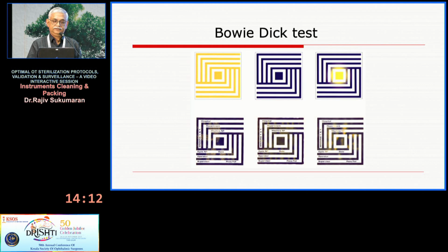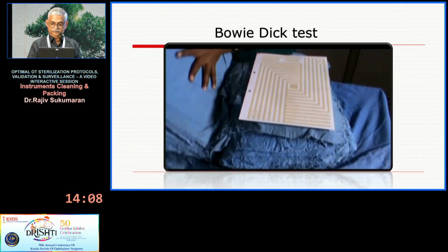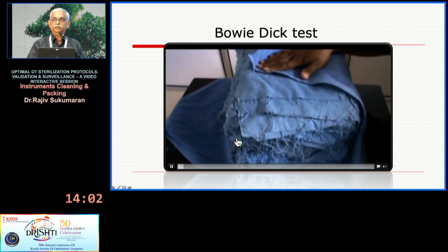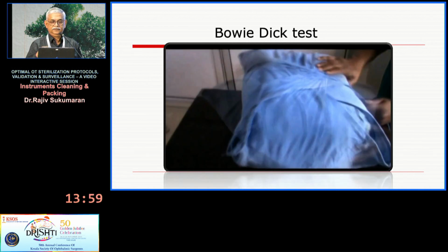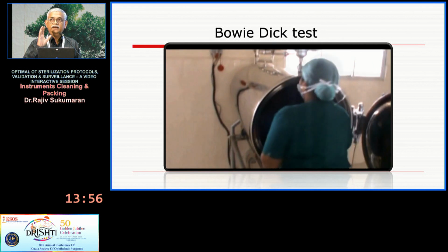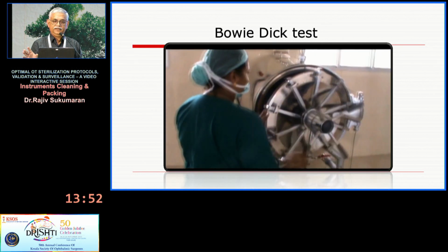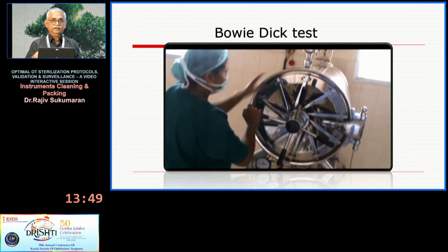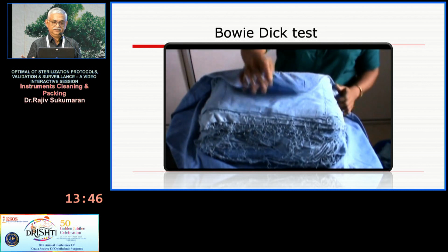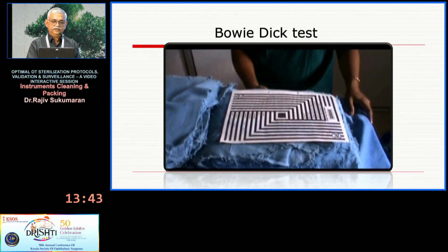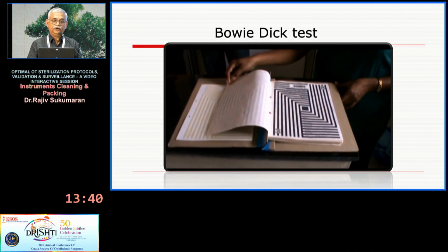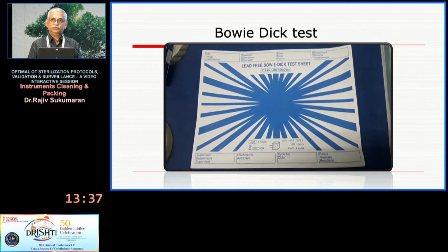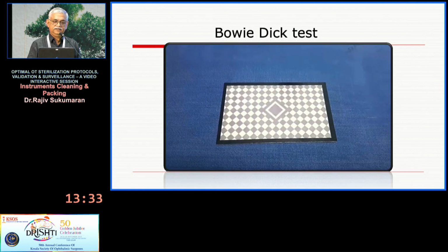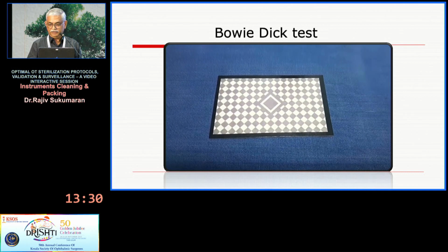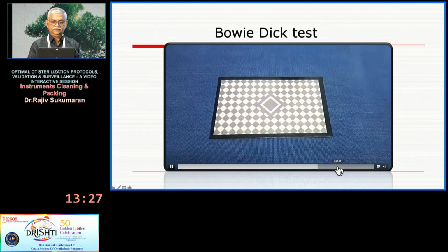Class 2 is Bowie-Dick. How the Bowie-Dick is done is, the Bowie-Dick sheet is kept between sheets like this, packed like this, and run in an empty load. No other load should be there, only these packs. It is usually done immediately before the sterilization happens. And the color change should be uniform like this and documented to prove that your autoclave machine is working. And these are the different models and designs which are available commercially.